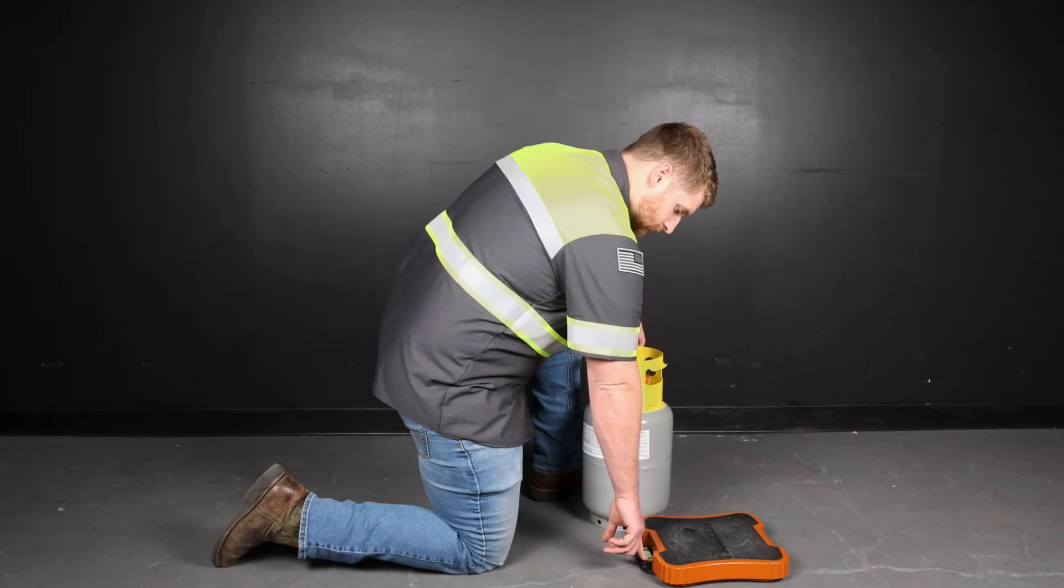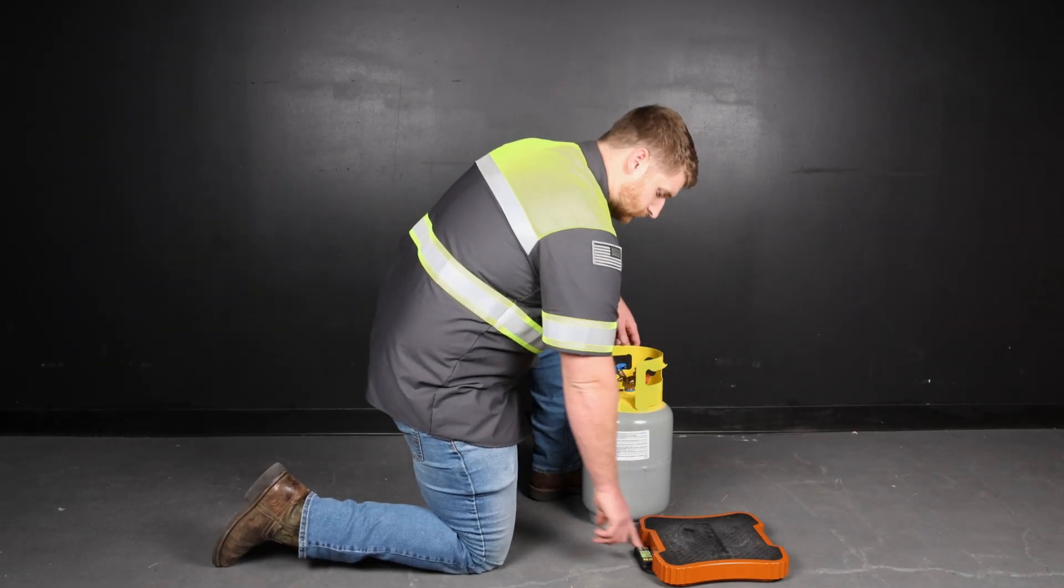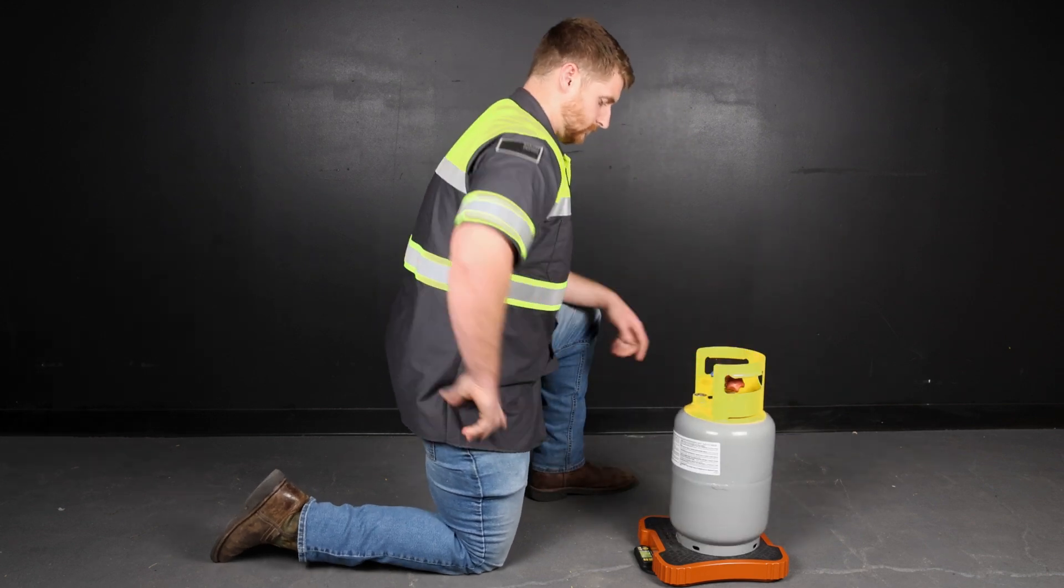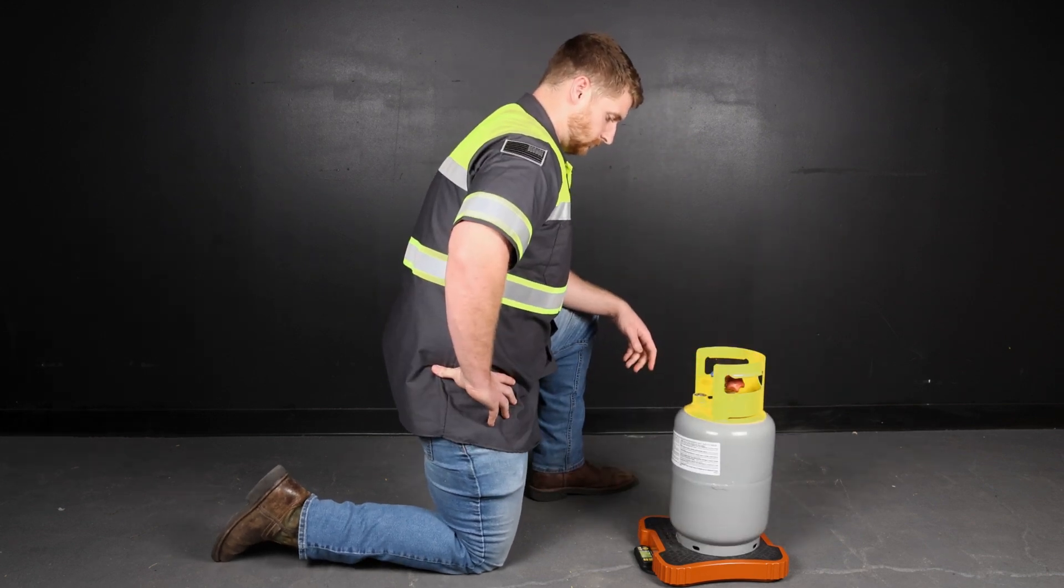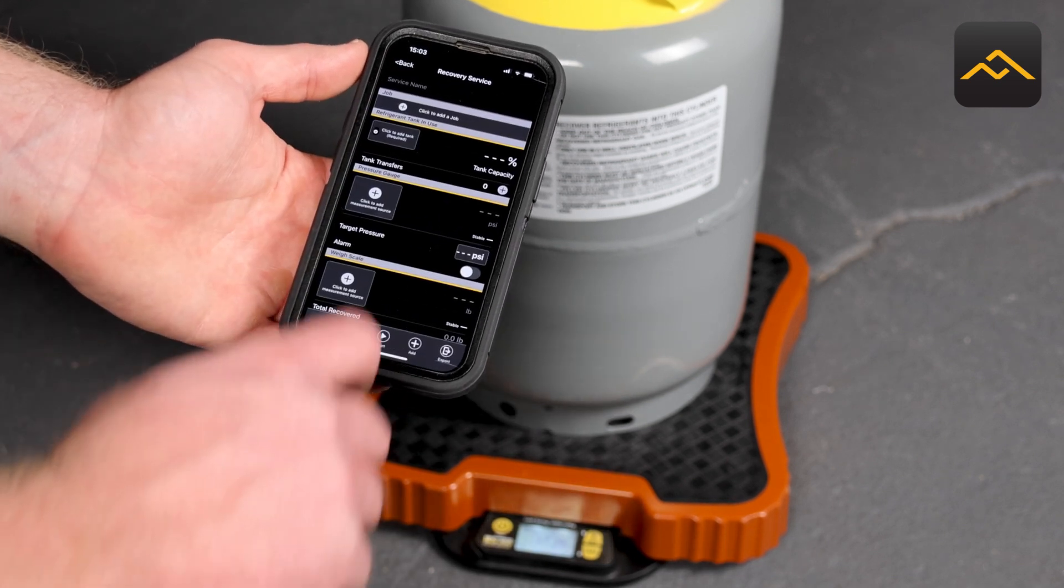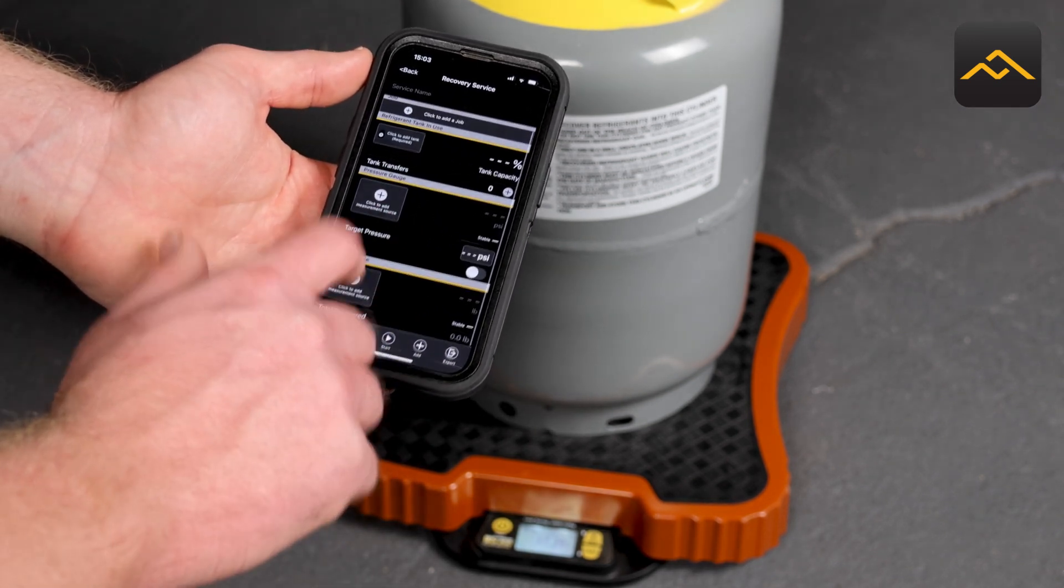Using a high-accuracy refrigerant recovery scale along with pressure temperature charts will help you safely fill the cylinder. In addition to these tools, HVACR service apps, like the Appion Central app, can help you understand the safe cylinder capacity for each refrigerant you might be working with.